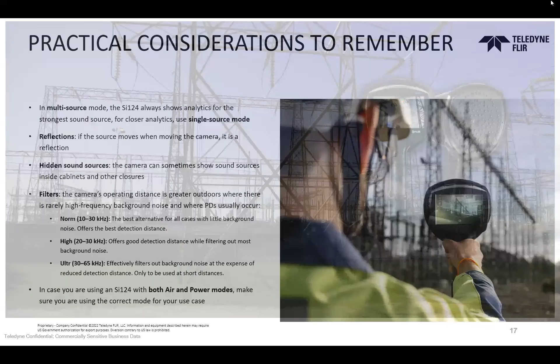The camera has a similar function to the LD Plus camera for leak detection, including the multi-source mode. For example, in a substation, it's recommendable to start with multi-source to find if there are different partial discharges, like isolators in parallel, and then go part by part switching to single source. The camera will discriminate the smaller sources and go to the most fundamental one. You need to take snapshots of every one of them.